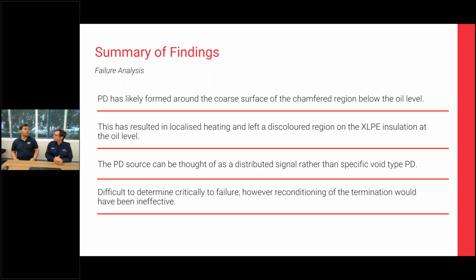It's one of the things that when Brody and I did the breakdown and everything, what we were expecting to see was quite a large discharge site due to the amount of energy given off in partial discharge signals. When we broke it down, we couldn't easily tell that it was rough or that there could have been discharge around those points.